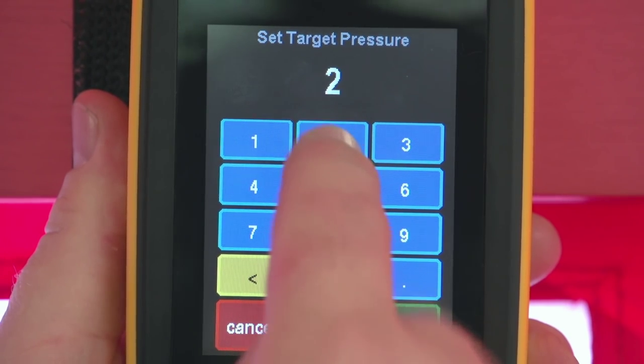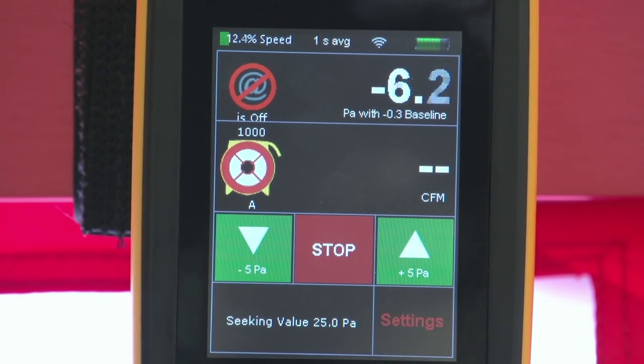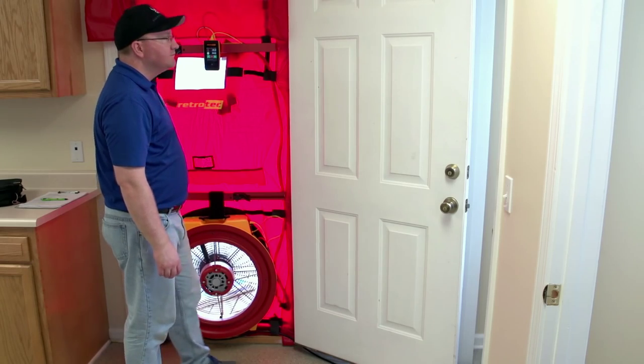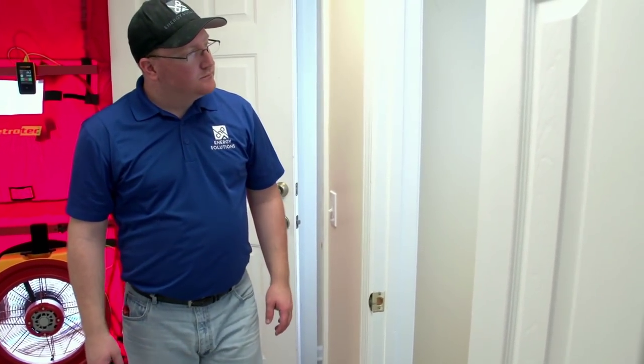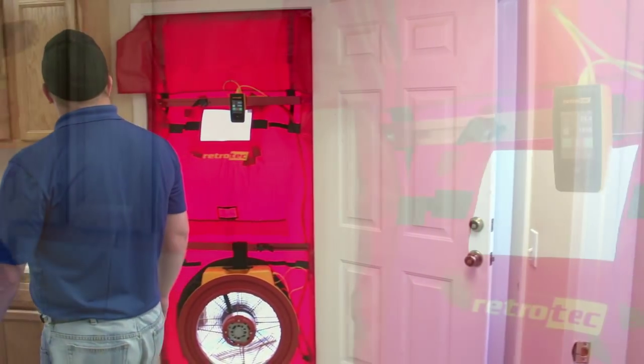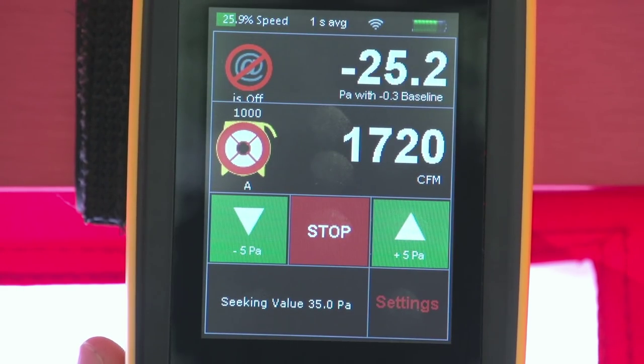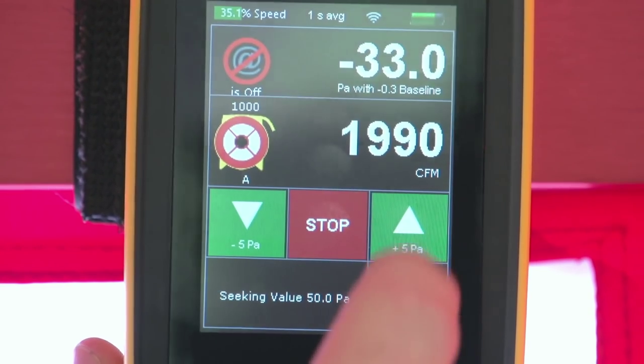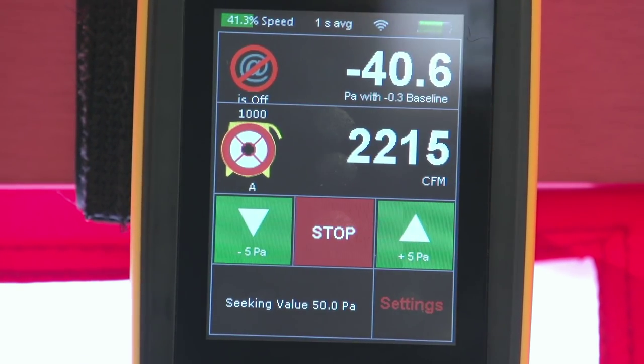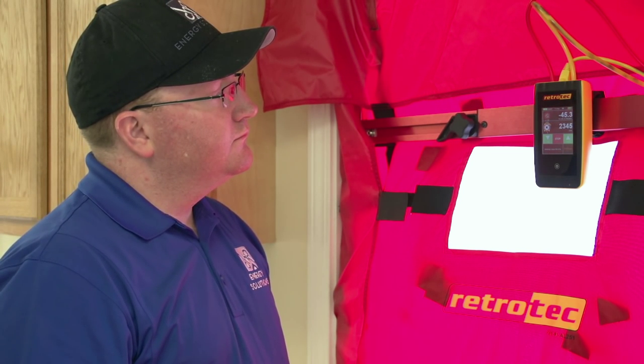Press Set Pressure, enter 25 Pa, and then press Set. The fan will start automatically and speed up until 25 Pa is reached. Take the time to perform a walkthrough of the home to make sure that nothing negative has occurred by the fan starting. If everything looks good, continue to depressurize to 50 Pa either by pressing the up arrow or by stopping the test and using the Set Pressure button and entering 50 Pa. Once 50 Pa is reached, record the CFM rate from Channel A.